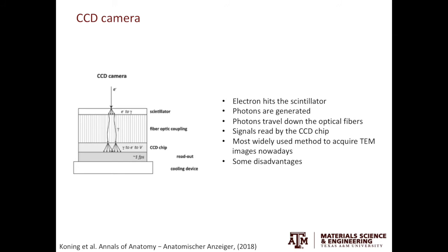On the left is a schematic of a CCD camera. From top down, you have the scintillator, which converts electrons into photons; then you have optical fibers to transport photons; and lastly, you have the CCD chip to read out photons and give you the signals. When an electron hits the scintillator, it will generate multiple photons, and those photons will transport along the optical fibers and get read by the CCD chip.